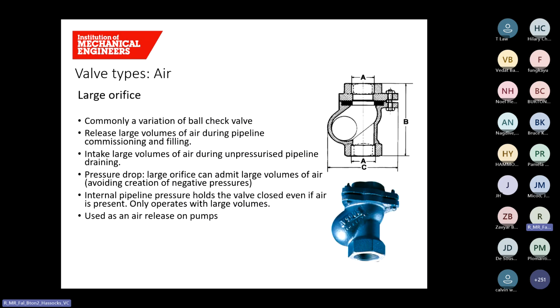Orifice air valve is a variation of the ball check valve. It's used for releasing large quantities of air from a pipeline, and so it's often used on pumping stations for commissioning and also after maintenance to refill the pipeline. If the pressure drops suddenly, the larger orifice can admit large volumes of air very quickly. The internal pipeline pressure holds the valve closed if small amounts of air are present. But when there's a lot of air in the system, the valve opens and it's released to atmosphere.